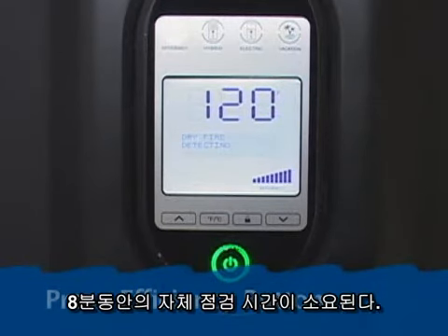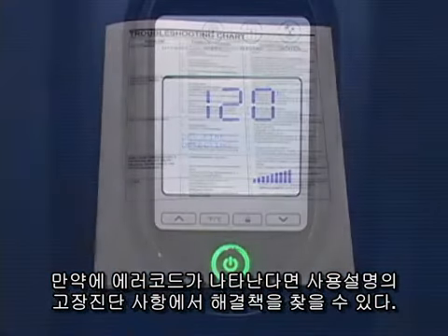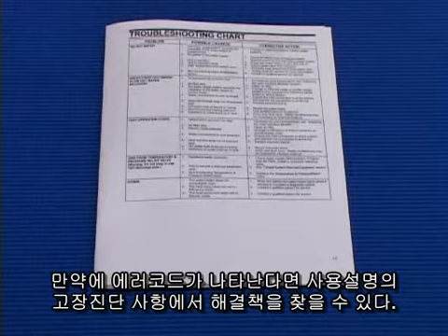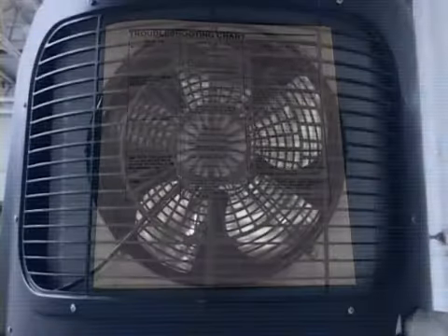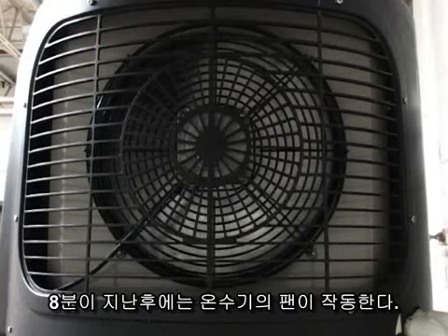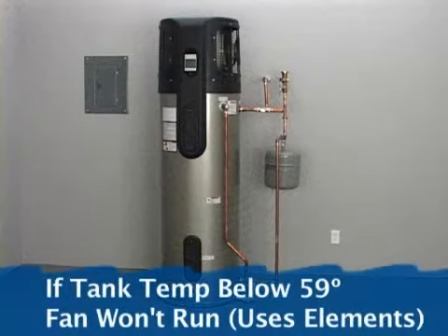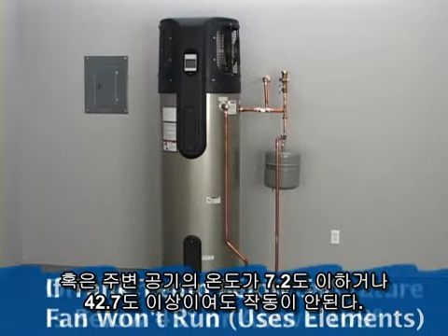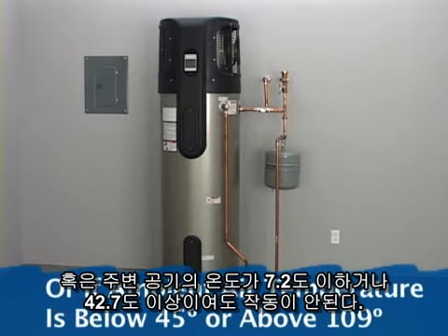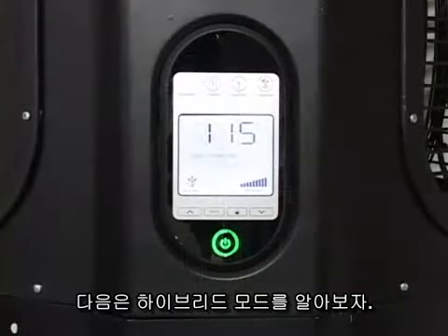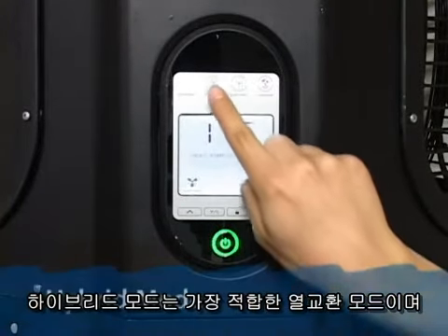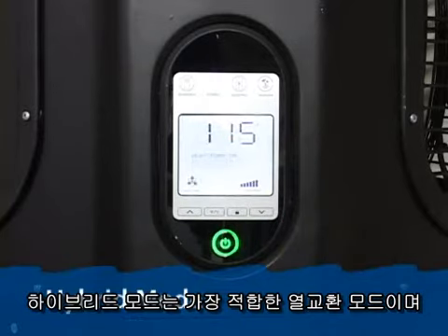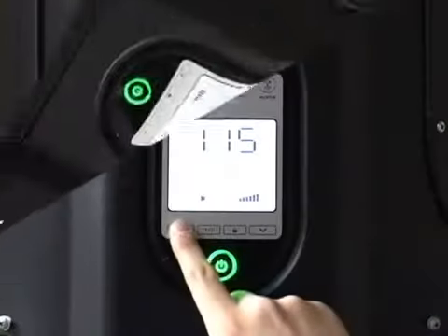The heat pump water heater will begin a diagnostics check that will take about 8 minutes. If an error code is displayed, refer to the installation instructions. After 8 minutes, the heat pump's fan will turn on. The fan will not run if the tank temperature is below 59 degrees, or if the ambient air temperature is below 45 degrees or above 109 degrees. Now set the desired operating mode. The hybrid mode offers the best combination of efficiency and hot water delivery.